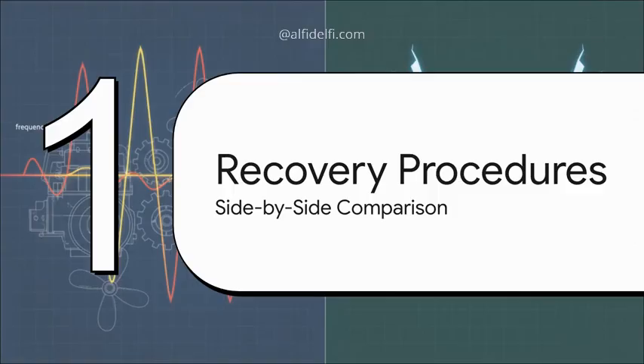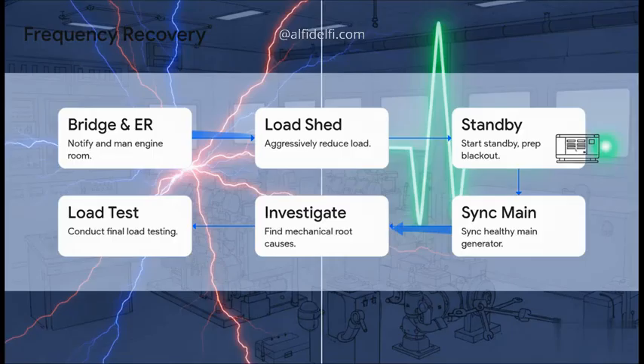Section 5. Comparing recovery procedures. For frequency fluctuation, your absolute primary mindset has to be blackout preparation. Once you've notified the bridge and got the engine room manned, you've got to immediately begin aggressive load shedding. You'll go ahead and start the standby generator, but, and this is absolutely crucial, do not synchronize it yet. Anticipate the blackout by preparing the emergency generator.